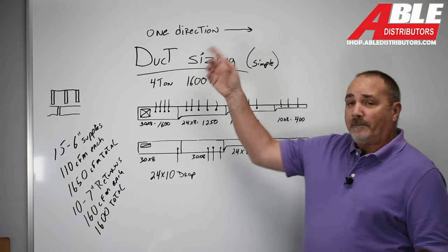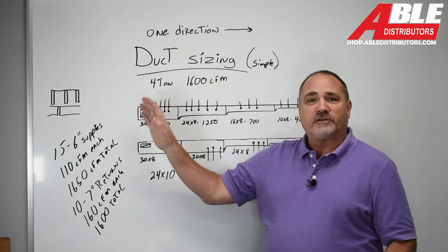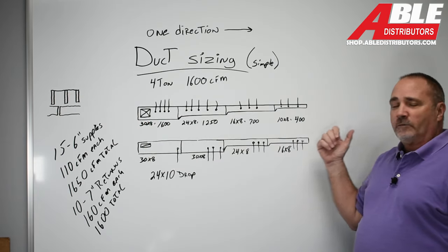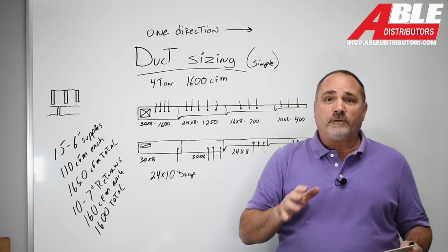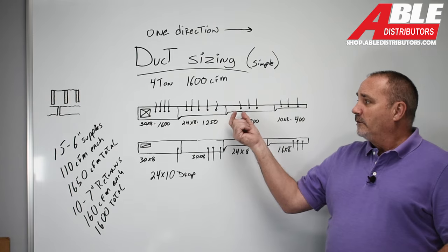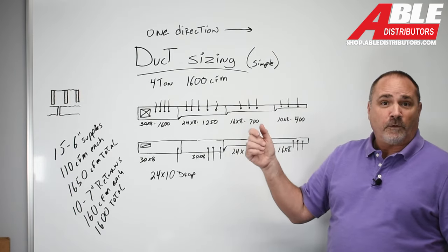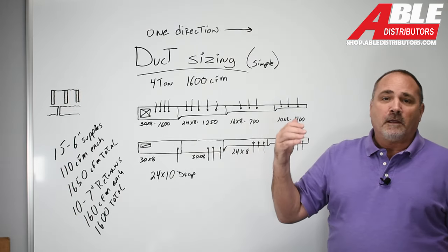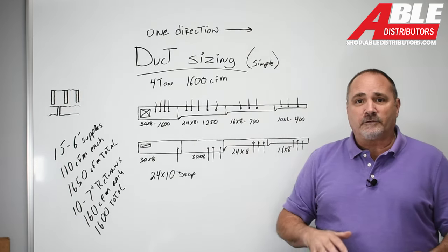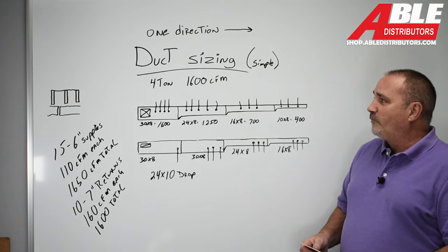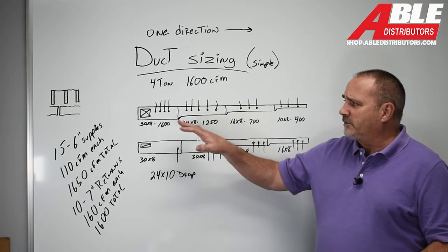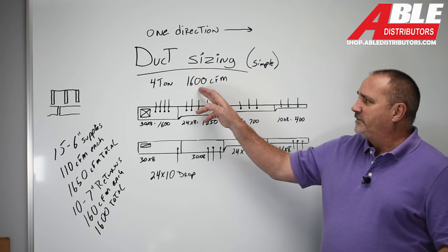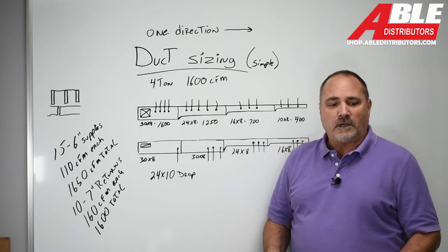This is one direction, not the band. It just means that the furnace sits at one end of the house. The ductwork goes all the way across. I'm going to do another video where the furnace sits in the middle, the ductwork goes both ways. And then I might do another video on zoning because when I was a contractor, I zoned a lot of houses. People always loved it. So before I get started, the system we're looking at here today is one way. It's 1600 CFM or a four ton.